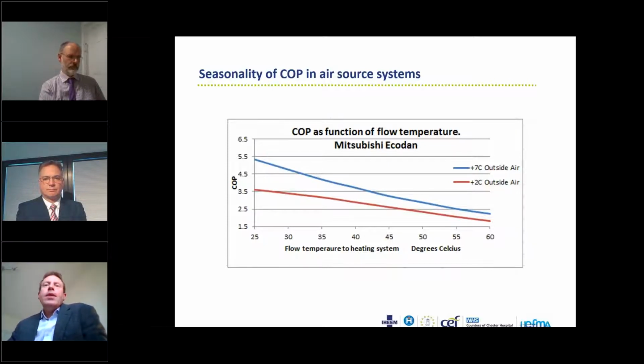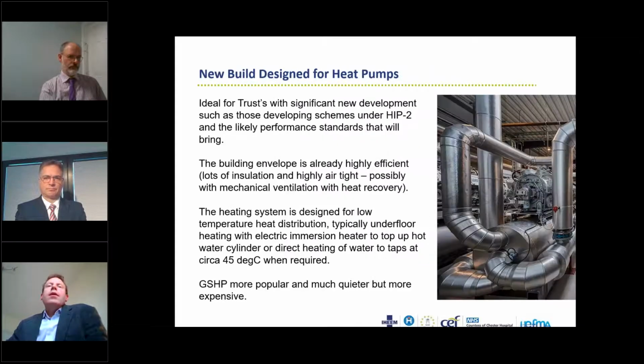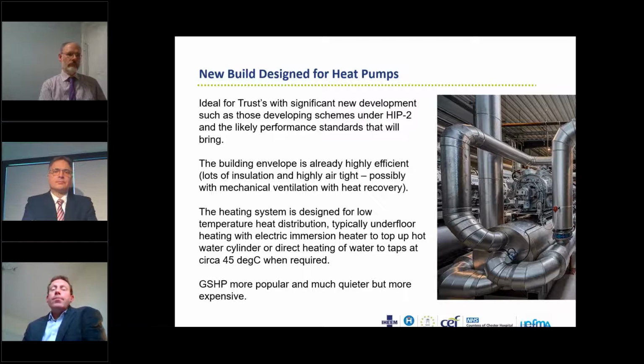Next slide, please. And this, oh, 2 slides forward. Well, the previous slide makes the point that the output temperature of the heat pump also affects its efficiency. So the higher the output temperature, the lower the efficiency. So with new build, there's the HIP2 program around, and there's a number of trusts which are looking at designing new builds. Heat pumps are better suited to lower temperature systems. So where we're designing new healthcare facilities, we have a wonderful opportunity to look at building engineering solutions which are inherently low temperature distribution systems, because they better suit the future technology.